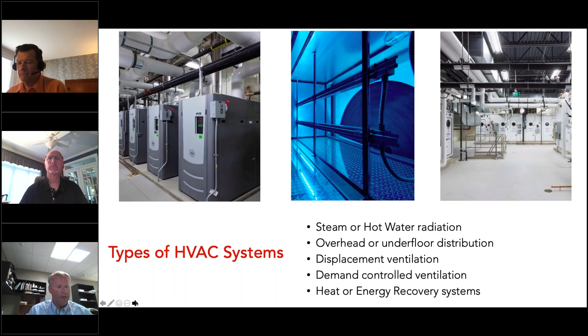We do a lot of smoke testing in buildings when we do our assessments to see where the outside air is being distributed, where the supply air grills are, where the return air grills are, and whether the air is short cycling, just going from supply right back to the return and not even going into the occupied zone. You can see the photo on the bottom. That's a smoke test. Really the air is just hanging right above where a student would be sitting. It doesn't even reach the student. It just literally sits there and goes right back to the return.